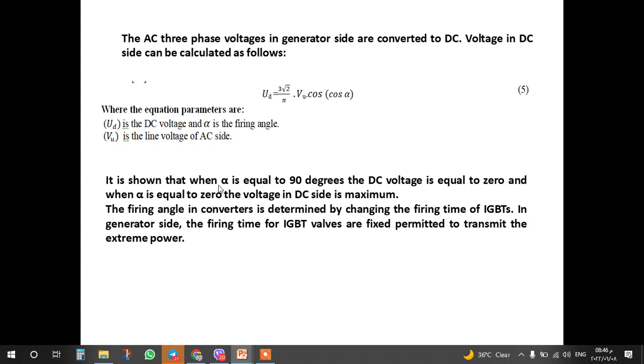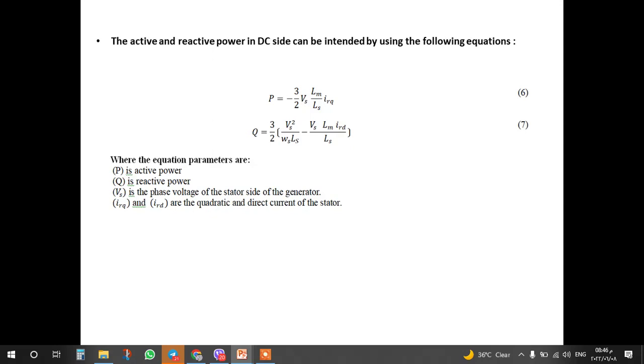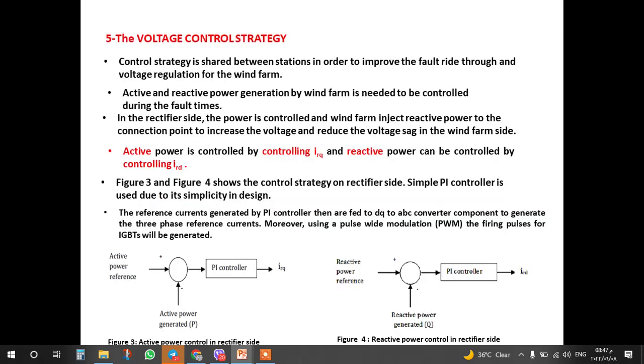It is shown that when alpha is equal to 90 degrees, the DC voltage is equal to 0, and when alpha is equal to 0, the voltage on the DC side is maximum. The firing angle in the converter is determined by changing the firing time of the IGBT on the generator side. The firing time for the IGBT valves is fixed, permitted to transmit the external power. The active and reactive power on the DC side can be calculated by using the following equation.